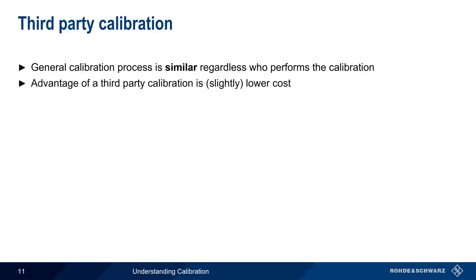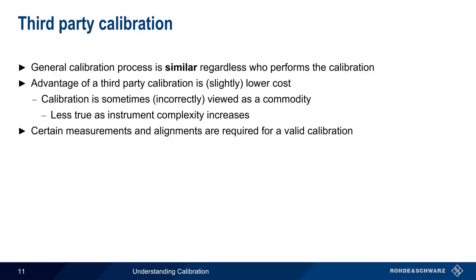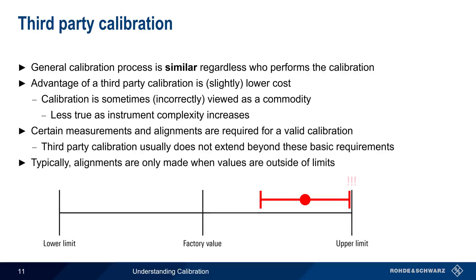We'll start by looking at third-party calibration. Because the general calibration process is similar regardless of who performs a calibration, third parties are sometimes able to offer calibration services for test and measurement instruments. The advantage of having calibration performed by a third party is slightly lower cost. Calibration is sometimes viewed as a commodity — that is, that all calibration is essentially the same — but this is not entirely correct, and is especially true in the case of modern or more complex instruments. While third-party providers can perform the basic measurements and alignments needed for a valid calibration, these providers typically perform only these measurements and alignments, and alignments are normally only performed when values are outside of the acceptable limits, regardless of how close values may be to those limits. This is especially problematic if the instruments used by a third-party provider have relatively large measurement uncertainties.